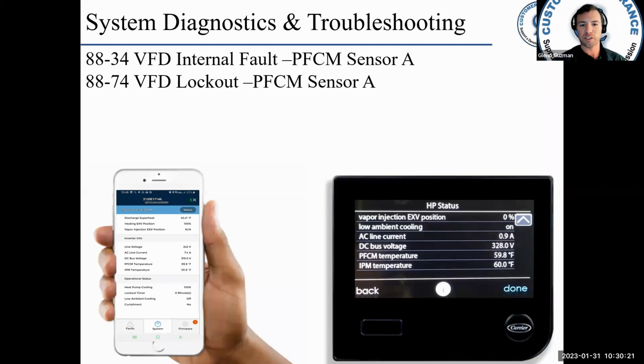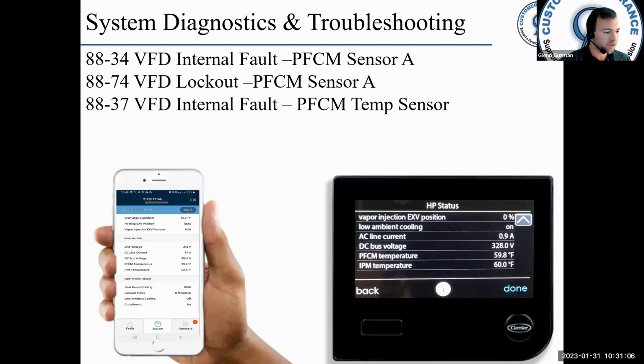8834 and 8874, this is the VFD internal fault, PFCM sensor A, and the corresponding lockout. Kind of the same thing, 3 occurrences of the 8834 within a 4-hour period gives you the 8874. Let's see, while the fault is active, the unit is inoperable. Once set, it is unlikely to go away and indicates VFD damage. Again, check your reactors, check for signs of overheating, check your high voltage connections. If all of that seems fine, then replace the VFD.